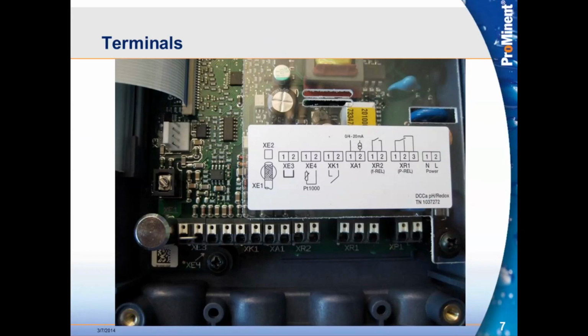Okay, just a really quick look at the terminal strip here. You see what we're getting into more and more. We have this clamp for that coax cable that's coming from the sensor, either pH or ORP sensors. Use our SN6, and here we're going to go open end. So that open end, you'll see on the diagram that's attached, the braided shield of that coax goes under this silver clamp over here on the left. Then the center conductor goes into the terminal that's right in front of that. So you have the center conductor. I would connect that first, maybe. It seems easier. And then the shield would get clamped underneath this kind of thumb screw here.